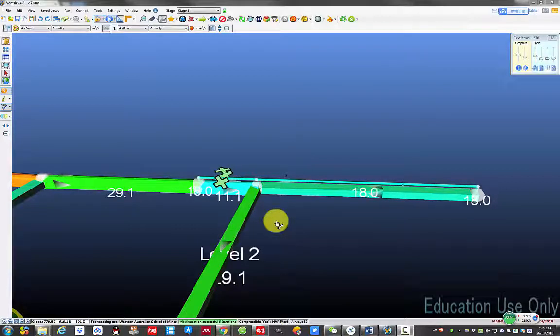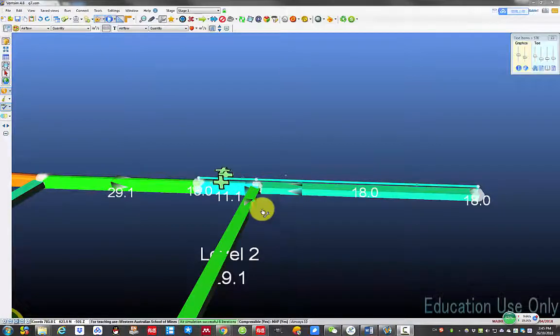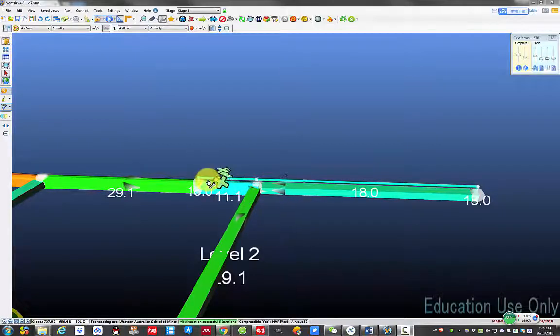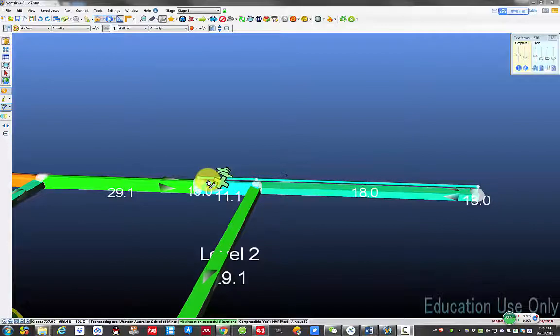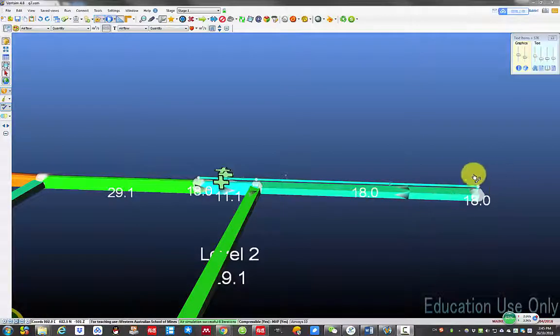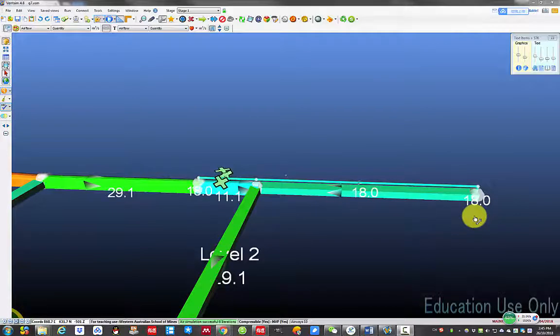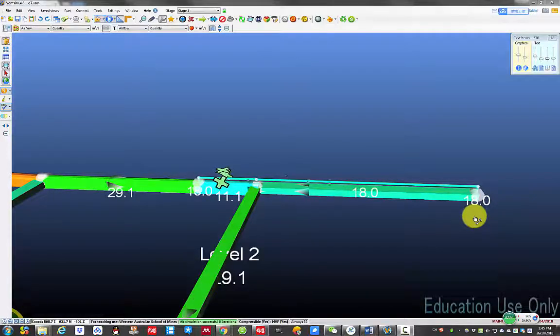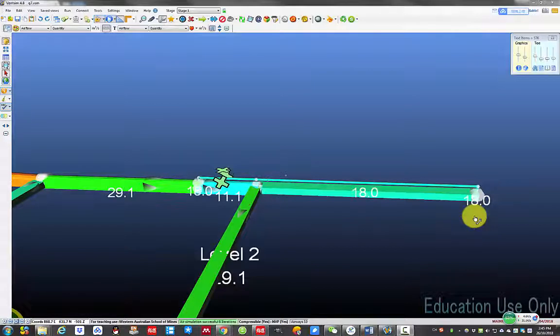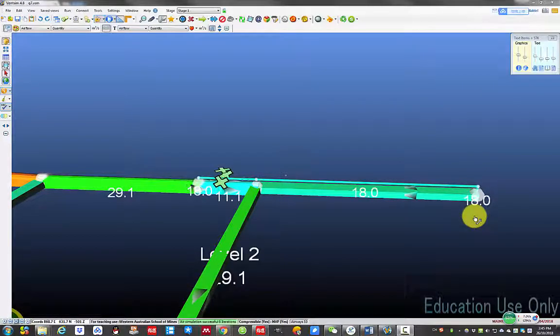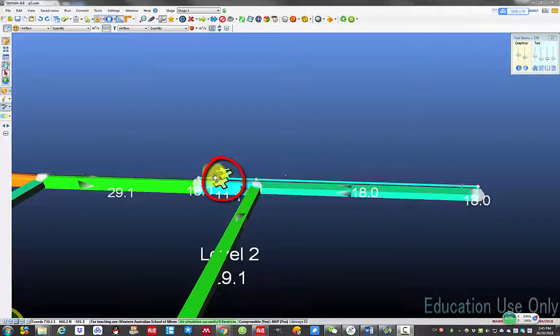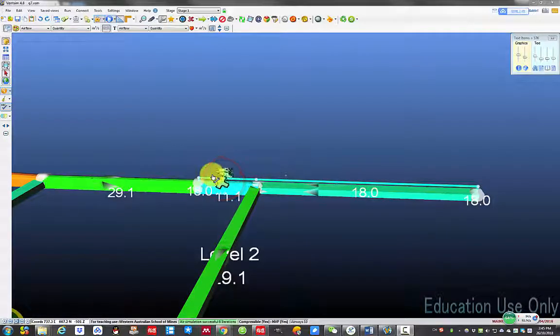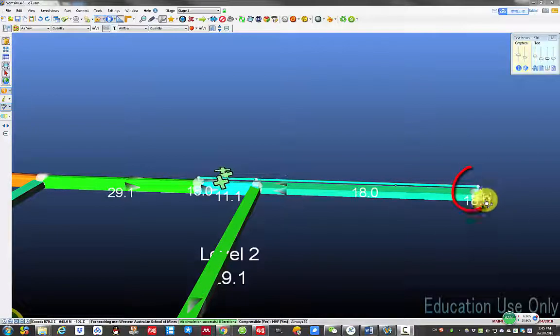There are two more things we need to consider. The first one is in this example, 18 cubic meter per second of air is provided at the beginning of the duct and most of them are pushed to the heading face here. But in most of the case, the amount of air you get at the face will be less than the amount of air provided by the fan due to duct air leakage. In that case, you will need to increase the air quantity at the fan until you get enough air at the heading.